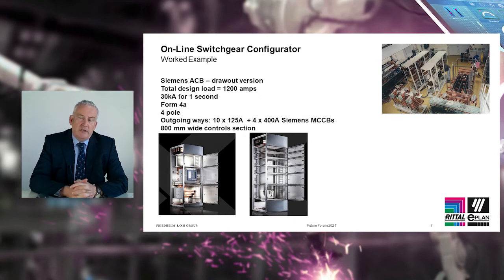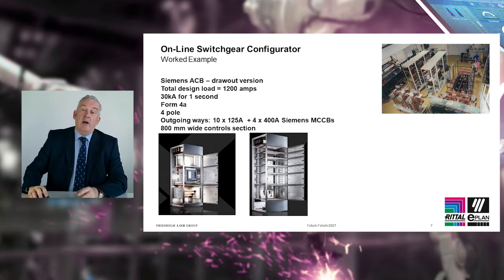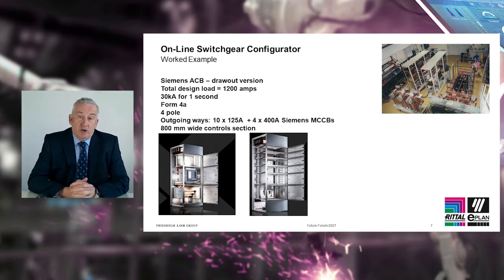What I'm not showing you today is the technical manual, where we can work out the compartment sizes for each circuit breaker rating, be it 125 amps or 400 amps. Those compartment sizes are 300 millimeters high for the 400 amp MCCB and 200 millimeters high for the 125 amp. Also, at the end of the switchgear, there's a control section which is 800 millimeters wide and will contain the PLCs and the automation controls. So now we've got the worked example details, or specification.